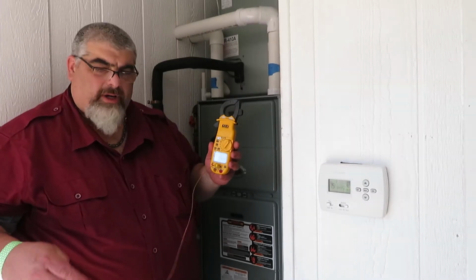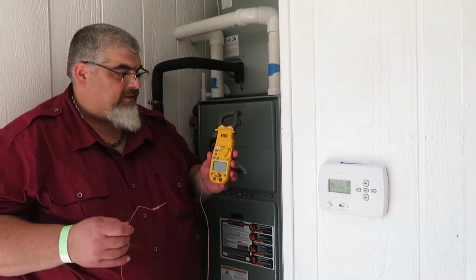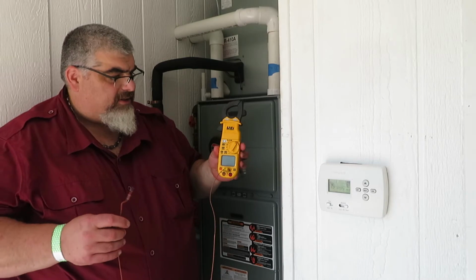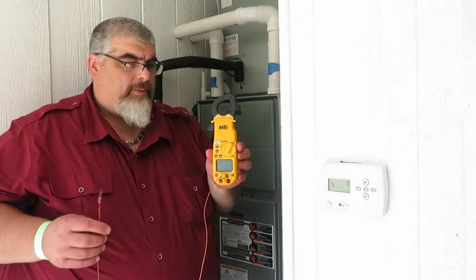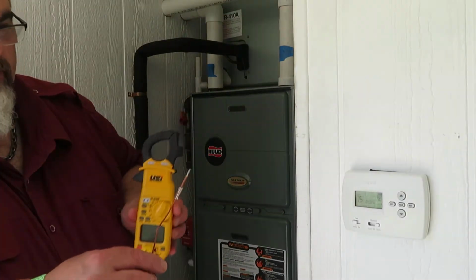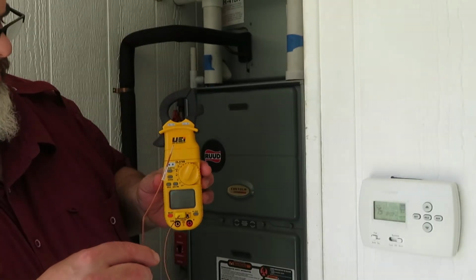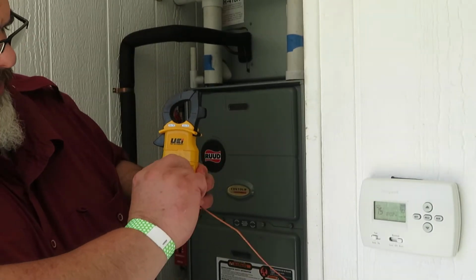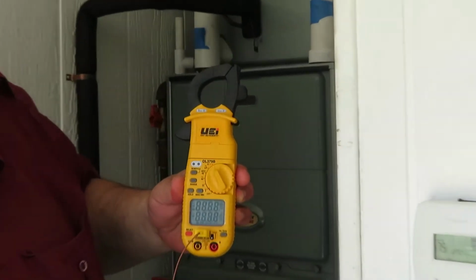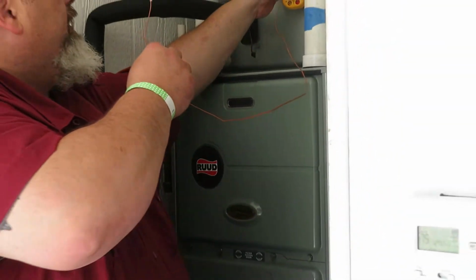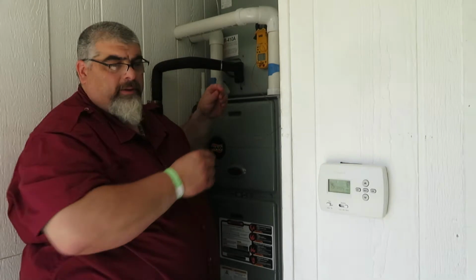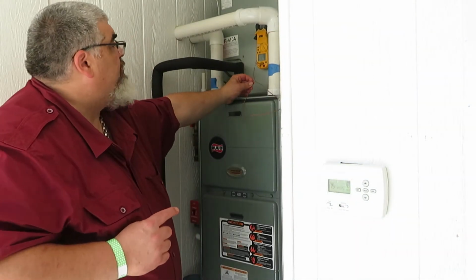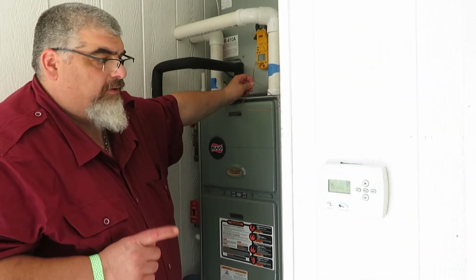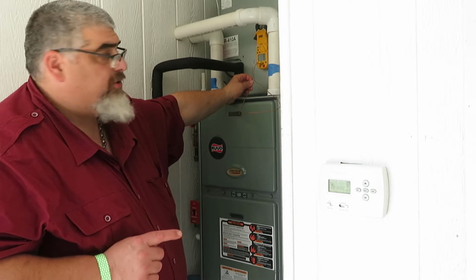Alright, so we're going to demonstrate today how to do a temperature rise test. To do the temperature rise test, you need a digital multimeter that reads temperature and your K-type thermocouple thermometer. You're going to turn your meter to temperature, and a couple things we're going to go over real quick before we conduct this temperature rise is, number one, this specific furnace needs to be in high fire for 10 minutes to reach steady state efficiency.